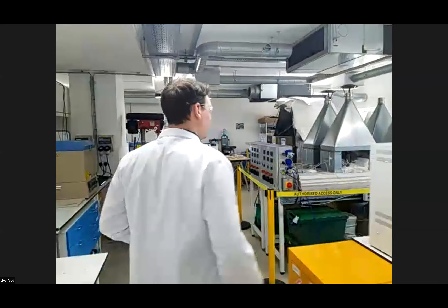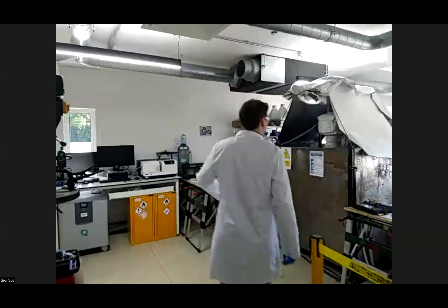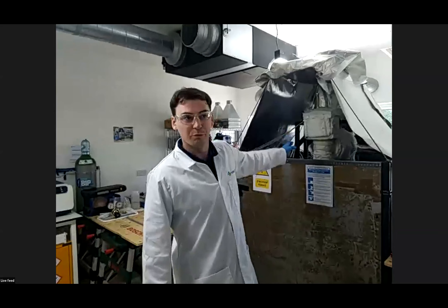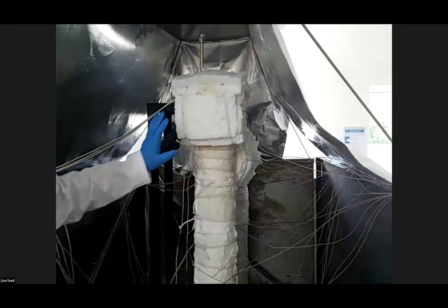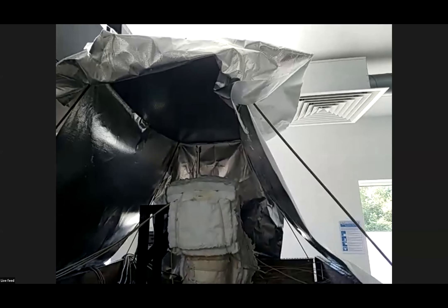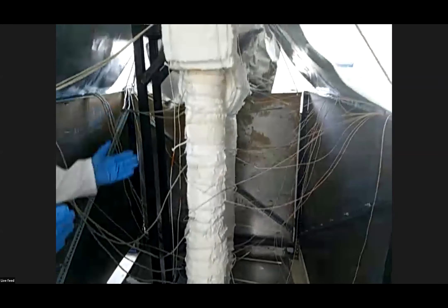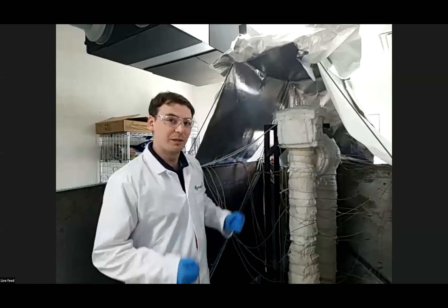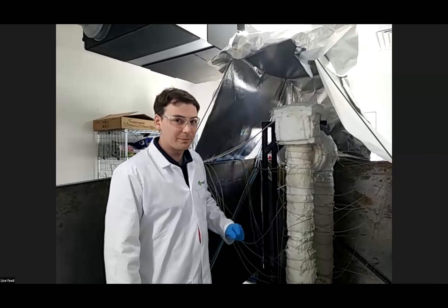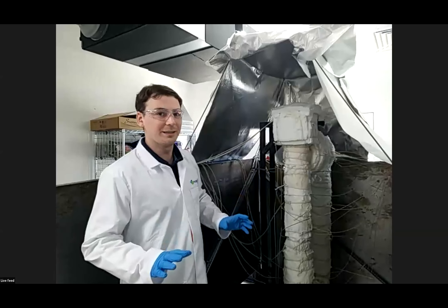These pins are all one temperature and not flowing, but in the reactor the coolant needs to flow. So in our rigs area we've built kilo-scale and flowing corrosion rigs — and more interestingly, we've been able to get to 20-kilo-scale flow loop rigs. This is our biggest rig to date. It's steel with a large amount of insulation to keep it hot. The purpose is to validate our thermohydraulic modeling: we have big heating elements down one side and small heating elements on the other to generate a temperature difference, driving natural convection — so we don't need pumps in the main body of the reactor. It's been up and down in temperature multiple times, and crucially — it doesn't leak.